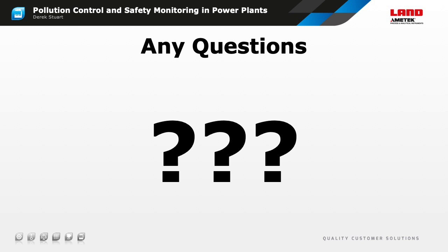You said that infrared temperature sensors can only measure the surface temperature of the fuel. Is there any way to measure the temperature of coal within a storage pile? That would be really nice if it was possible. Unfortunately, I don't know of any non-contact measurement that can look inside a coal pile. An X-ray thermometer would be wonderful if one existed, but I've never come across a practical technology for that. So really, the only way to make a measurement of the temperature within the stored fuel is to use a physical probe, such as a thermocouple, and push that into the coal pile.